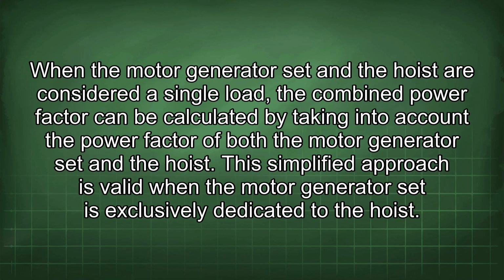When the motor generator set and the hoist are considered as a single load, the combined power factor can be calculated by taking into account the power factor of both the motor generator set and the hoist. This simplified approach is valid when the motor generator set is exclusively dedicated to the hoist.